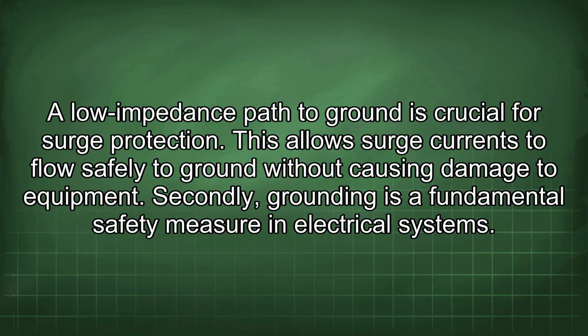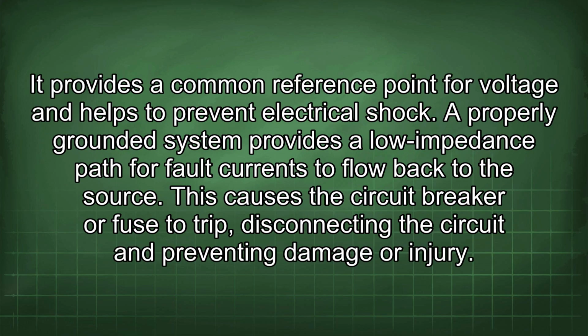Secondly, grounding is a fundamental safety measure in electrical systems. It provides a common reference point for voltage and helps to prevent electrical shock. A properly grounded system provides a low impedance path for fault currents to flow back to the source. This causes the circuit breaker or fuse to trip, disconnecting the circuit and preventing damage or injury.